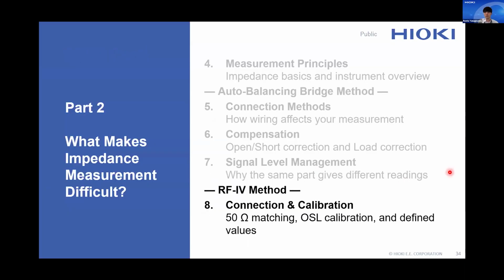Okay, now let's move to the RF-IV method. If you are working at higher frequencies, this is your instrument. But the measurement principle is fundamentally different from the auto-balancing bridge. And so are the techniques for getting accurate results. Here, connection and calibration are inseparable. You cannot talk about one without the other.